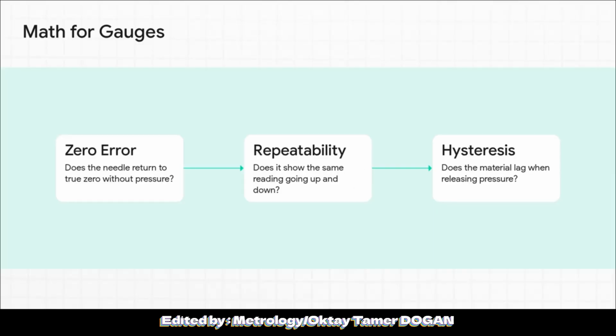Interestingly enough, the older EN 837-1 standard used to demand it be 4 times better, but the modern Euramet standard settled on a strict 2 times ratio, which is enough to ensure total mathematical confidence. You can kind of frame this whole mathematical process like a lie detector test for industrial gauges. The Euramet standard forces laboratories to check 3 main vulnerabilities. First, they determine the zero error. Basically, does the needle actually return to absolute zero when there's zero pressure?